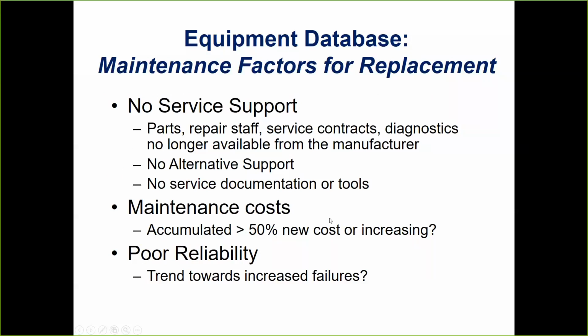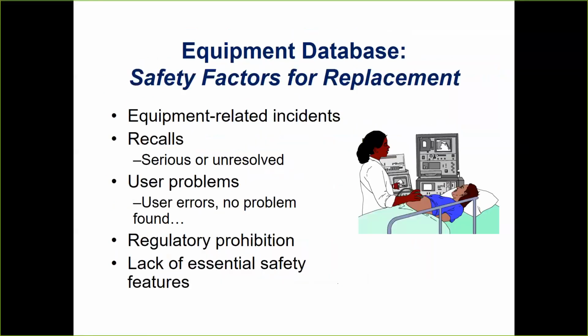Maintenance costs, as those accumulate, we have to consider replacement more so. Reliability, that's another one. In terms of safety factors, we're talking about equipment-related incidents that occur, adverse events that occur in your health system, recalls that are occurring, especially the serious ones that are unresolved, user problems, continuous problems with operation of equipment, maybe due to poor human factors, engineering, design. If regulations prohibit the use of the device, that's certainly a reason to replace it. And essential safety features.